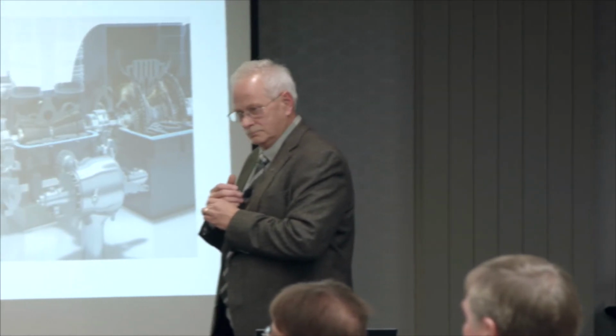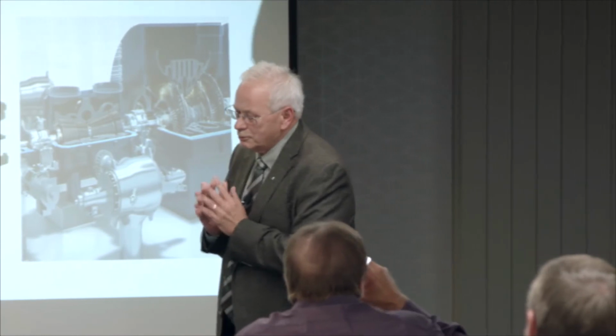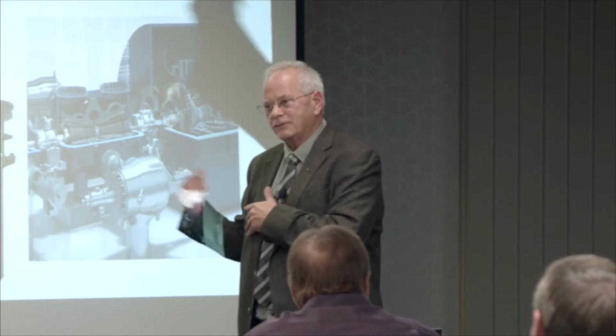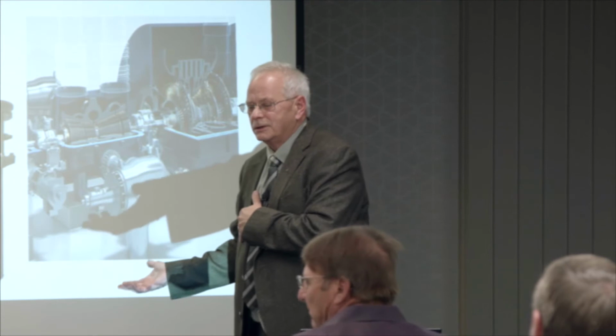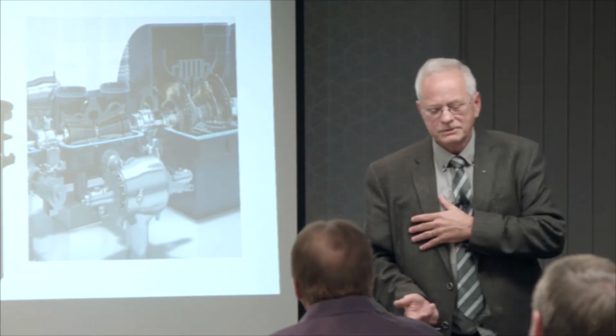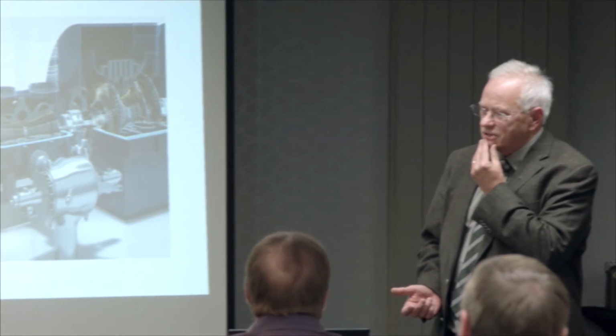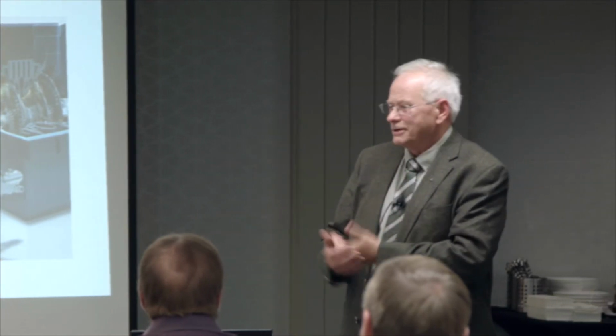Woody, I'm going to bug you again. Your reservoir of oil that you're talking about, and it's significant in size from the sounds of it. When you have to replace that, what's the cost of draining it out, containing it in something, taking it somewhere? Typically, we remove it during an outage and filter it and reuse it. But we're talking hundreds of thousands of dollars. I can't remember how much it is for oil, like 8,000 gallons, $3 a gallon.